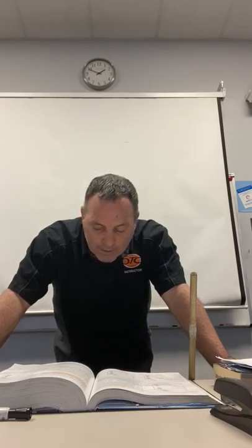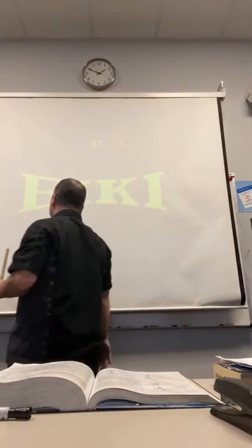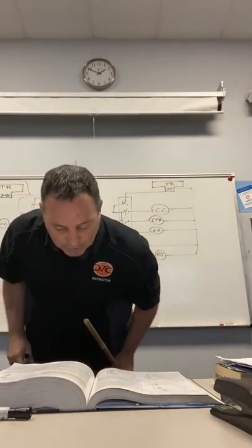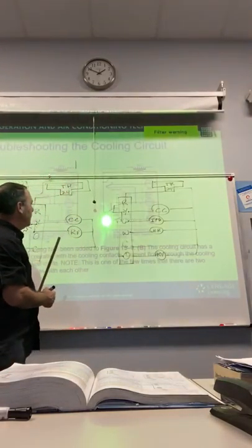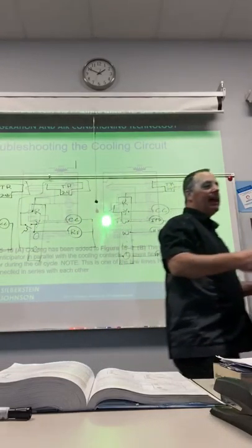Now, it should be restated the thermostat is nothing more than a set of switches. There is a manual selector switch with off, cool, and heat, and automatic temperature sensing component. When the conditions are correct, the thermostat will pass power on through the device. When the system is calling for heat, it goes to the heat relay. When it's cooling, it goes to the cooling relay.